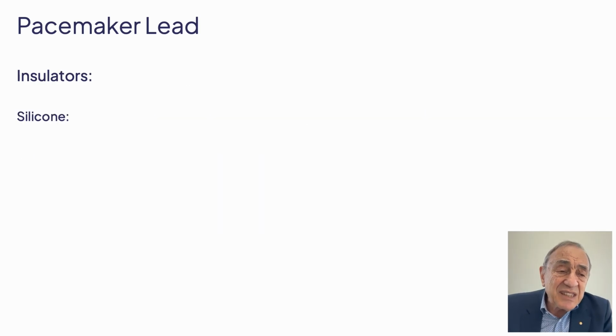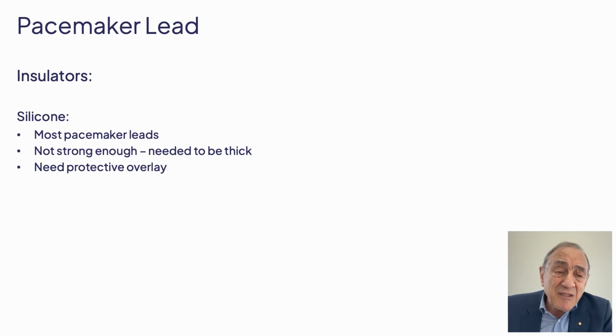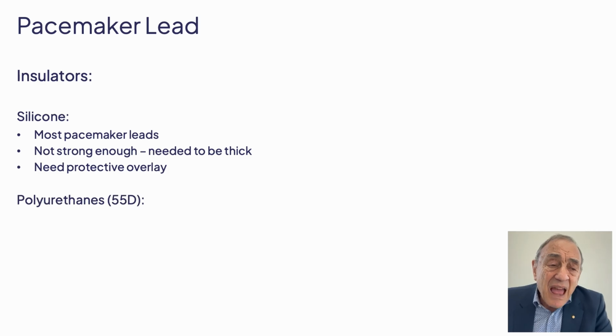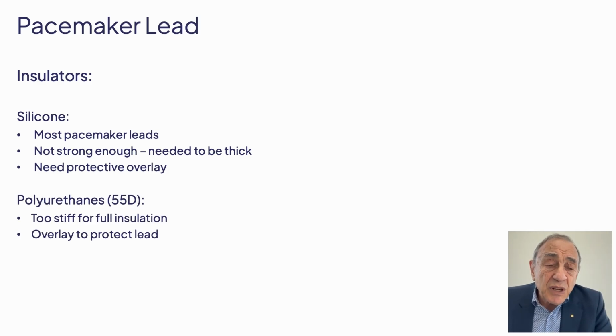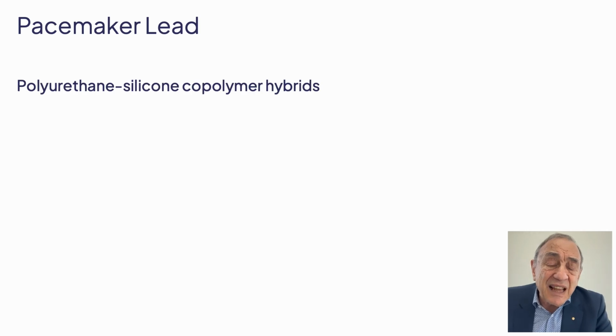So we have silicone rubber. Most pacemaker leads use it, though it's not strong enough and needs to be thick, but today we have better quality. However, it does require a protective overlay to prevent the breakup of the lead insulation, and we use polyurethanes, which are too stiff for full insulation but useful for overlay. A further insulation material is the hybrids.